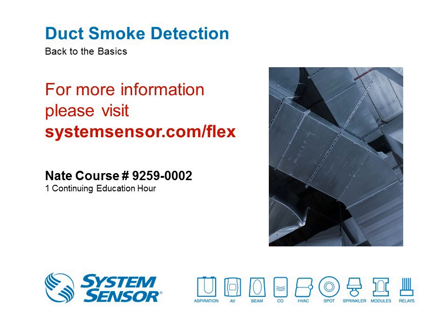Okay. All right. Let's see here. Duplicate kind of questions here. How about this? If a project calls for 100% area smoke detection, does the code require the fire alarm to shut down the air handling unit fan? Want me to repeat that one? No. Okay. Again, that depends on if it's being designed for NFPA 101 or International Fire Code, there's going to be some differences. In both cases, you're still going to have to shut down the fan, because they don't want to transfer smoke. So yes, it should shut down the fan.